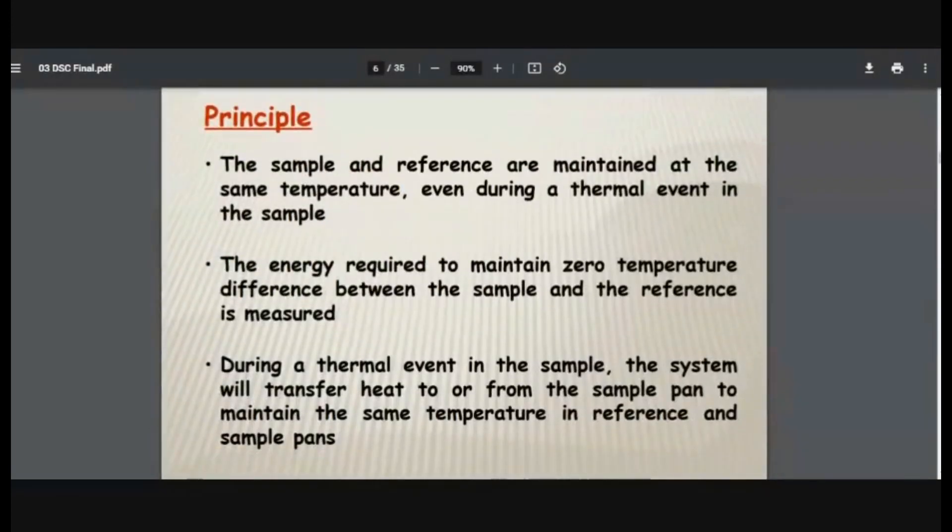Let us see what is the principle behind this technique. The sample and reference are maintained at the same temperature even during a thermal event in the sample. Now how will we do this? Suppose it is an endothermic process - that means energy, the sample is taking more. But still, sample temperature and reference temperature have to match. So what will we have to do? We will have to give much more energy to the sample, so that the temperature of the sample and reference matches. If it is an exothermic process, what you can do? Not only will you have to stop the energy which you are supplying to the sample, you have to, in a way, give the energy to the reference and check what is the energy difference.